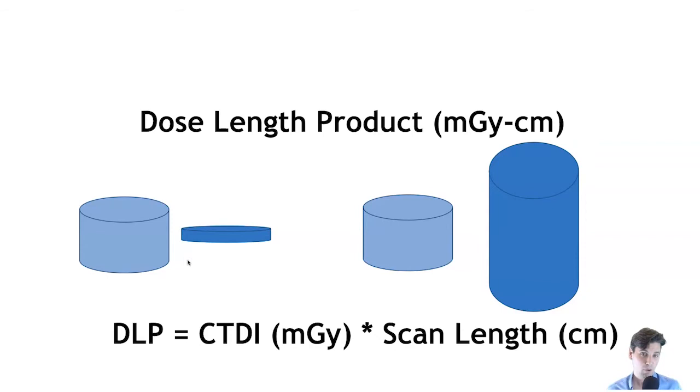So that's what we're talking about here, is we described CTDI already. CTDI is a measure of the radiation dose, the absorbed dose, for a given size. Namely, you can think of a given height along the patient direction. We call this usually the superior to inferior direction. So CTDI is normalized to some given length along this direction.